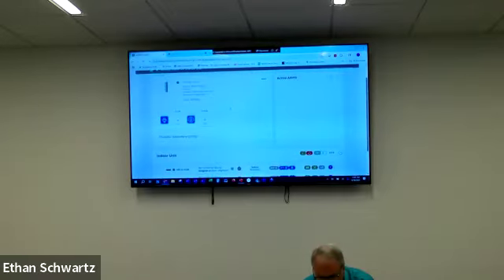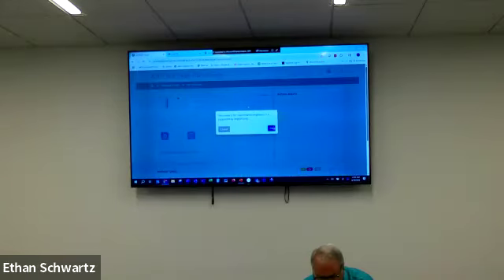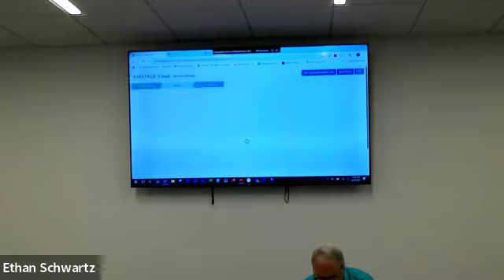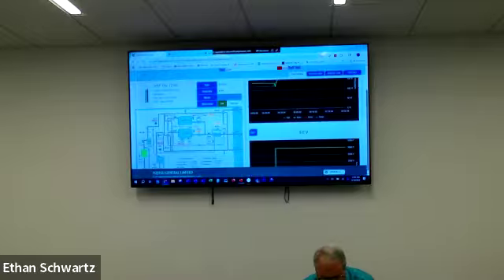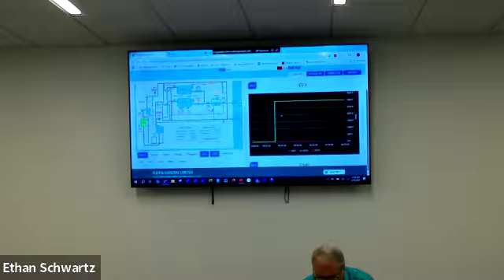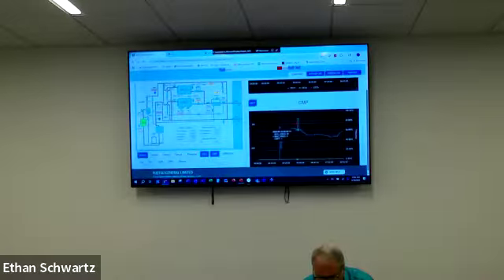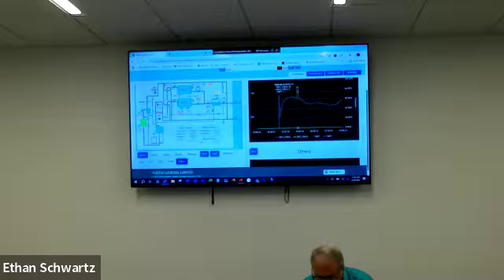We want to look at that. Then we can see what's going on with the piece of equipment. We can turn it on and off. And then we go to service. And there's our outdoor unit. And this one's just humming along. It's giving us these graphs. That's what's great about our service tool software right here. If we click others, we can see what is this little jump up right here. And that's because when we hover over it, it was in oil recovery mode.